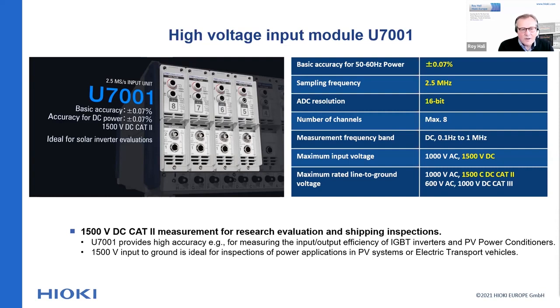And it has an accuracy of 0.07% for DC and 50 to 60 Hertz. The sampling frequency is 2.5 megahertz and the bandwidth is 1 megahertz. These specifications make these units very useful for DC and grid-related measurements. It further can be used for IGBT-based inverters measurement, like solar power conditioners, and that all for a very moderate price.